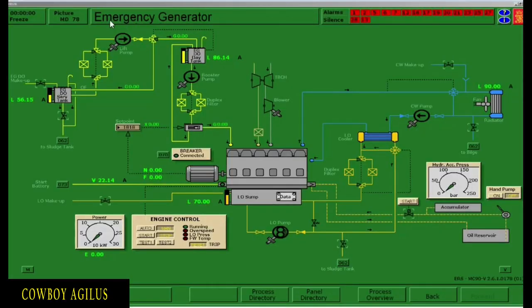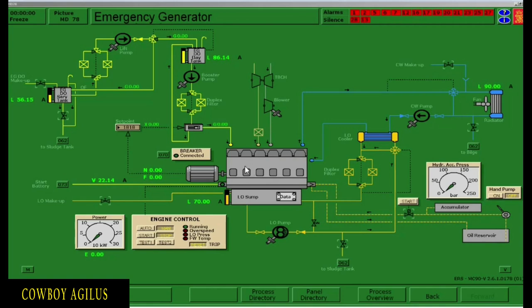Here is your emergency generator number 78. This is the engine. This is the cooling system. The emergency generator has a fan and it is using a radiator as cooling for the fresh water. The yellow lines in the diagram is the diesel system — the emergency generator is using diesel as fuel. This line is from the starting battery, so we will be using the battery to start the emergency generator. This is the lube oil system of the emergency generator.